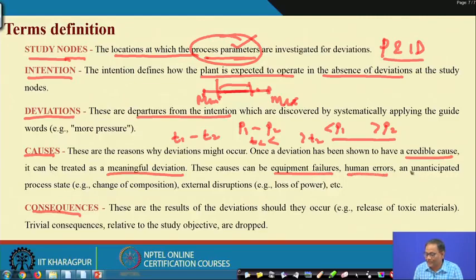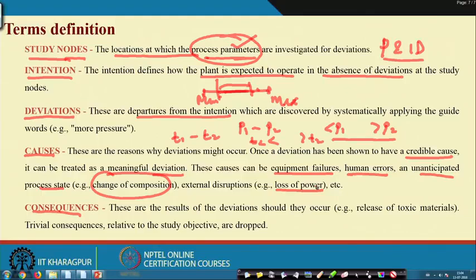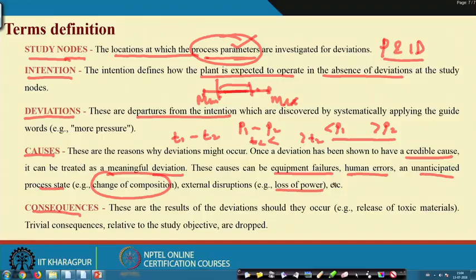There can be many trivial deviations and many significant deviations. Some deviations will require intensive causal analysis and many credible causes will be identified, and those deviations will be treated as meaningful deviations. Causes can be equipment failure, human error, an unanticipated process state like change of composition, or external disruptions. If over-pressure is the deviation, the immediate cause is pump overrun; digging further, the pump is allowed to run more than the design time because the timer does not work or the operator could not remove the switch.